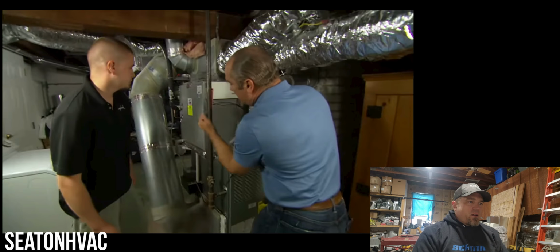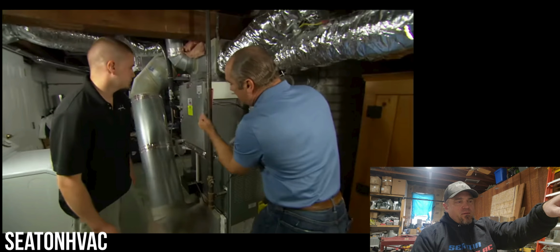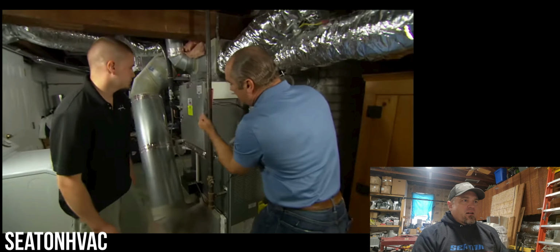One of them being that filter that they have in there, plus the way that return's tied in. So it's just kind of panned with a 1-inch filter wedged in there. There's some high static there, so I would have mentioned that right off the bat. And then also we'll get to the other part here, but the supply duct there just deadheads right off the coil, which is tons of air turbulence and adds a lot of static. So let's see what Rich has to say here.